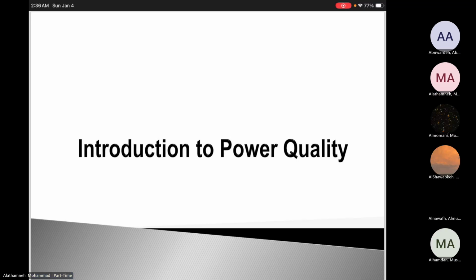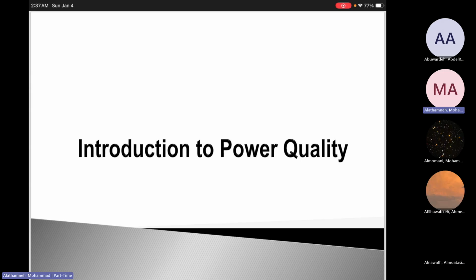When we used to have the old loads, based on RLC, for example motors with an equivalent RL circuit, or other loads like heaters, in the past there was no problem, or rather the problems were low with respect to modern loads, when we have renewable energy systems connected through three-phase inverters to the power system, and when we have rectifiers. All of these have a bad impact on the waveform of the currents and the voltage as well.